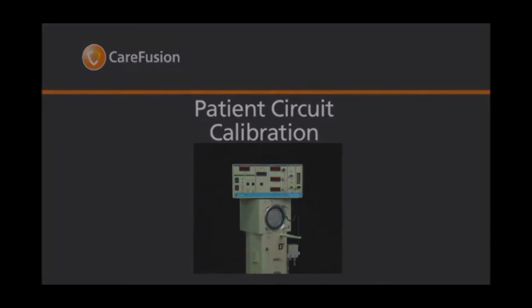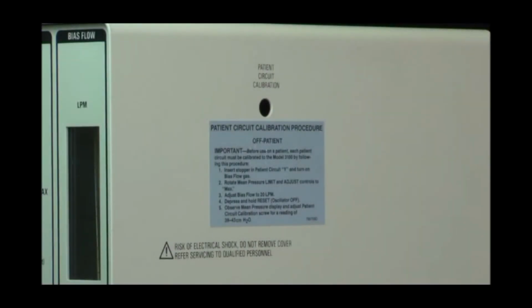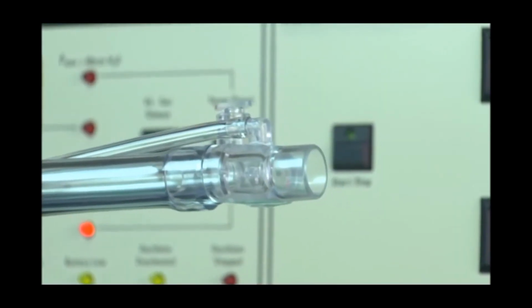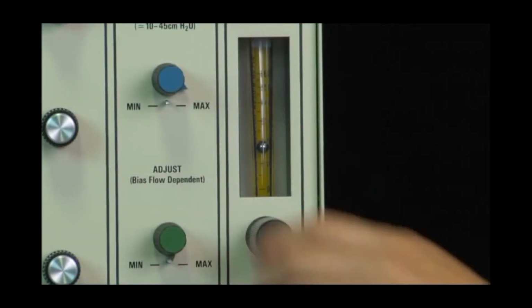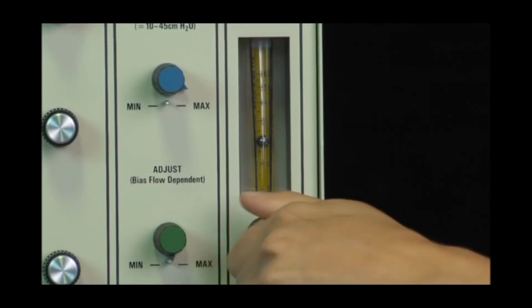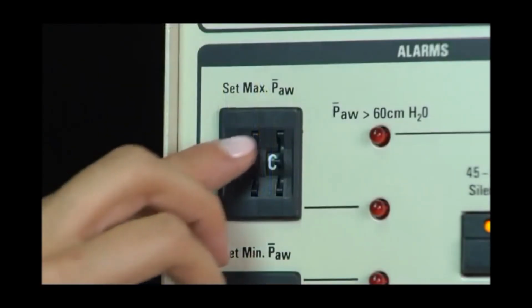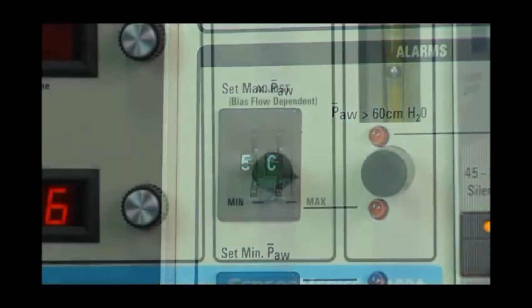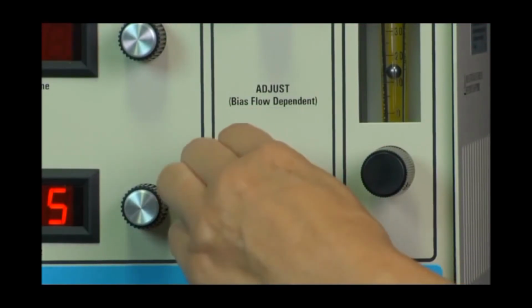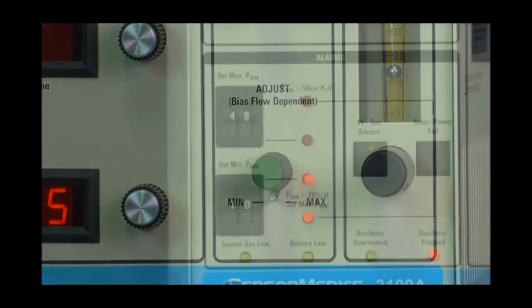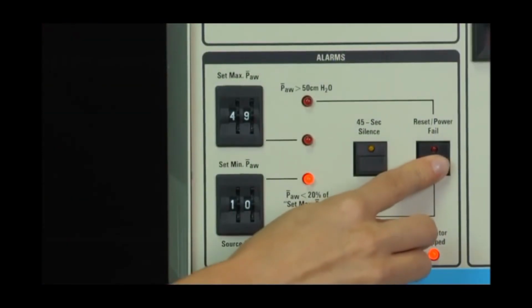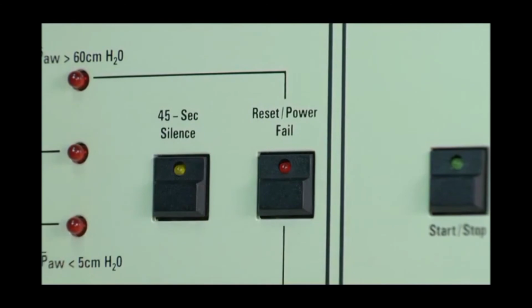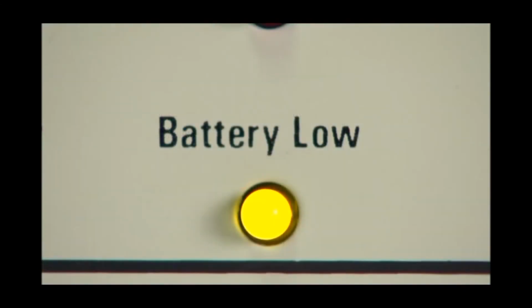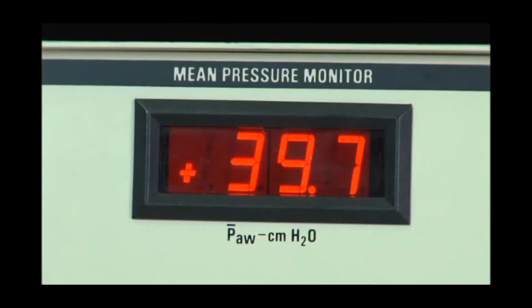Patient circuit calibration. To calibrate the patient circuit, locate the instruction label on the right side of the ventilator and follow these steps. Insert the stopper into the patient Y and adjust bias flow to 20 liters per minute. Set the maximum mean airway pressure alarm to the upper limit. Set the mean pressure adjust to the maximum setting by turning the control fully clockwise. Press and hold the reset button to allow the patient circuit to pressurize. It's normal for the battery low LED to illuminate when the reset button is pressed. The mean airway pressure should read 39 to 43 centimeters of water pressure.